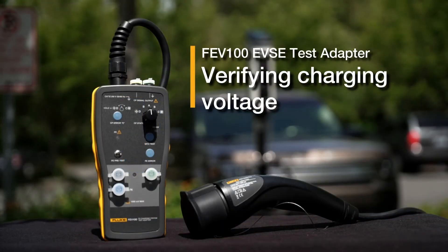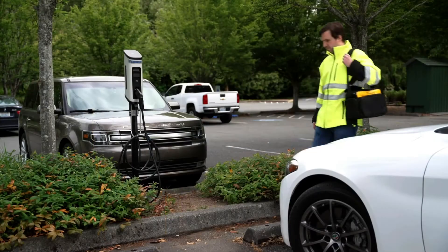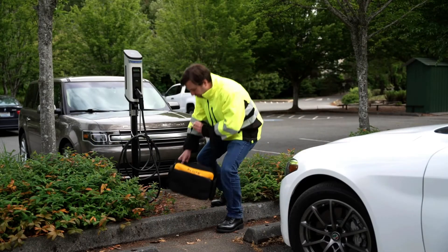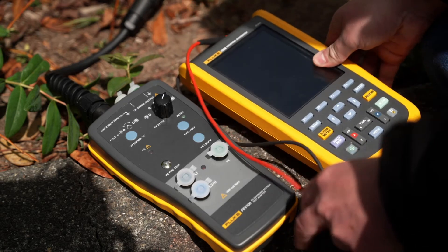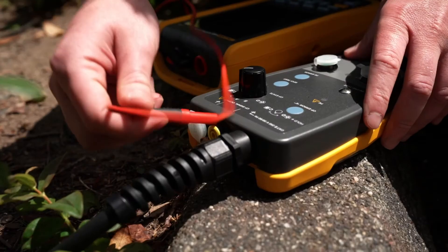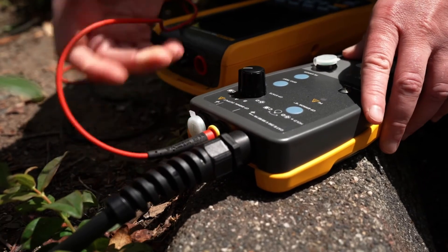Test different charging states of an AC Level 2 charging station with the Fluke FEV100 EVSE test adapter. The adapter simulates control pilot charging states of an electrical vehicle, so you can verify the charging voltage using a digital multimeter or scope meter.